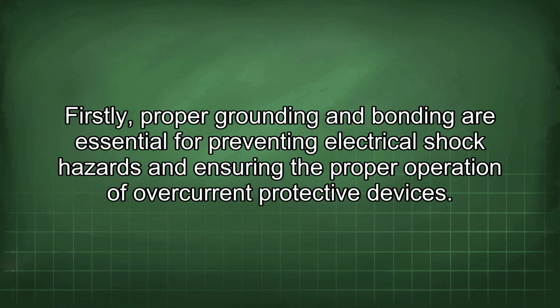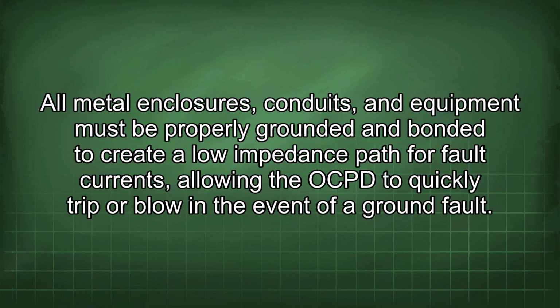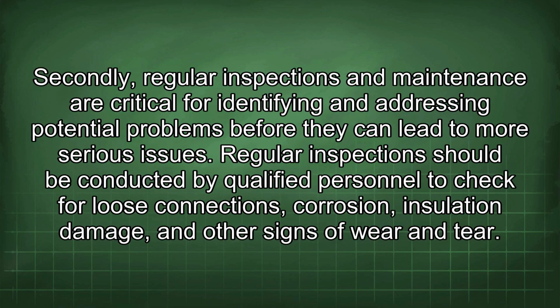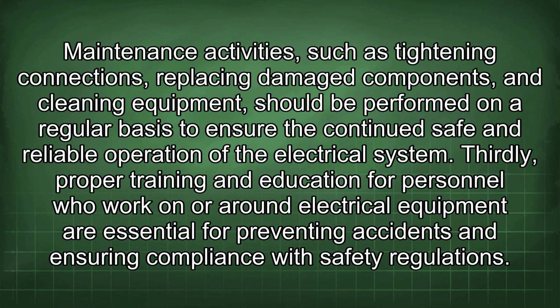Firstly, proper grounding and bonding are essential for preventing electrical shock hazards and ensuring the proper operation of overcurrent protective devices. All metal enclosures, conduits, and equipment must be properly grounded and bonded to create a low impedance path for fault currents, allowing the OCPD to quickly trip or blow in the event of a ground fault. Secondly, regular inspections and maintenance are critical for identifying and addressing potential problems before they can lead to more serious issues. Regular inspections should be conducted by qualified personnel to check for loose connections, corrosion, insulation damage, and other signs of wear and tear. Maintenance activities, such as tightening connections, replacing damaged components, and cleaning equipment, should be performed on a regular basis to ensure the continued safe and reliable operation of the electrical system.